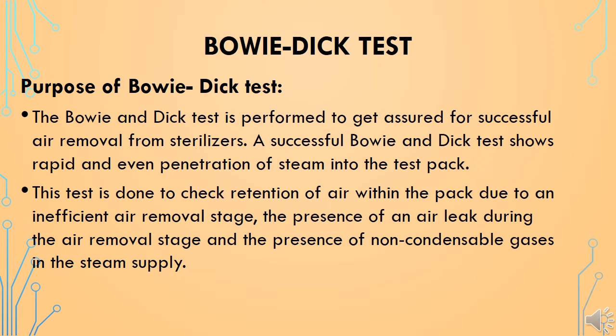First we will see the Bowie-Dick test. The purpose of the Bowie-Dick test is to get assured of successful air removal from the sterilizer. A successful Bowie-Dick test shows rapid and even penetration of steam into the test pack. This test is done to check retention of air within the pack due to an inefficient air removal stage, the presence of an air leak during the air removal stage, and the presence of non-condensable gases in the steam supply.